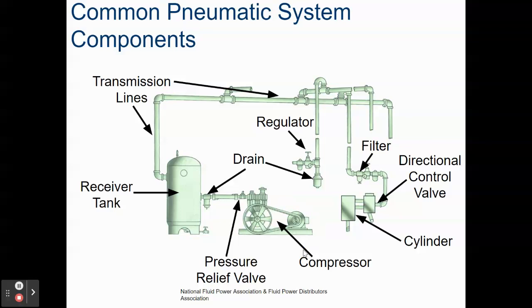First, we have a compressor, which is making our air. It's taking that air in from the atmosphere and compressing it. You guessed it. So it compresses it and puts it into this tank. Before it gets to the tank, there's a pressure relief valve. If something were to go wrong and there would be too much pressure, it releases that excess pressure so we don't have some sort of accident. It's not labeled, but there's probably also an additional pressure relief valve right here.